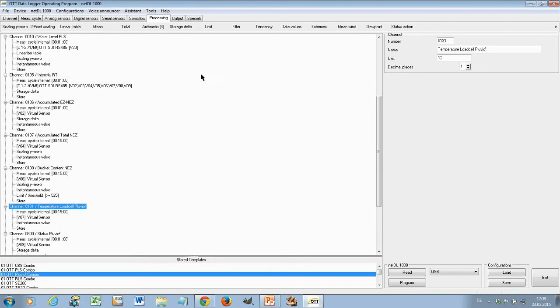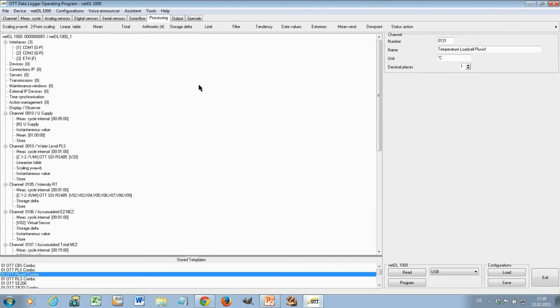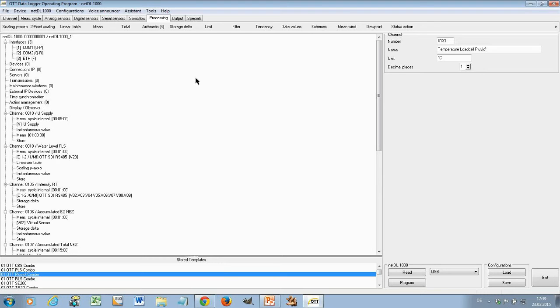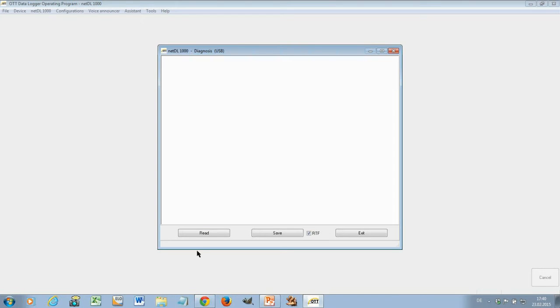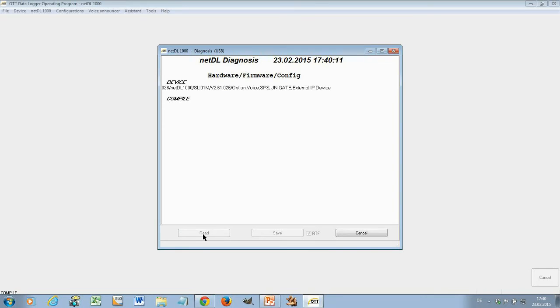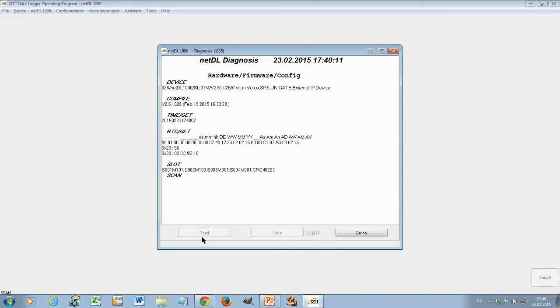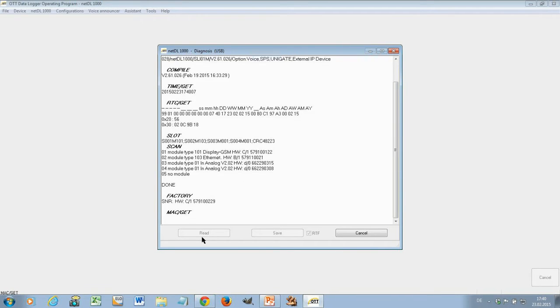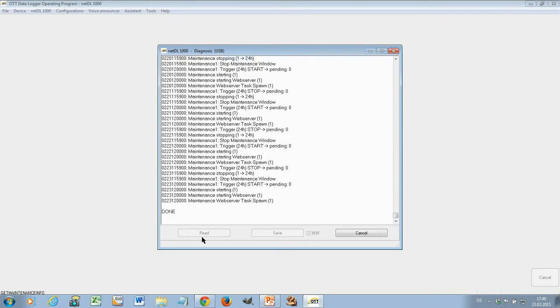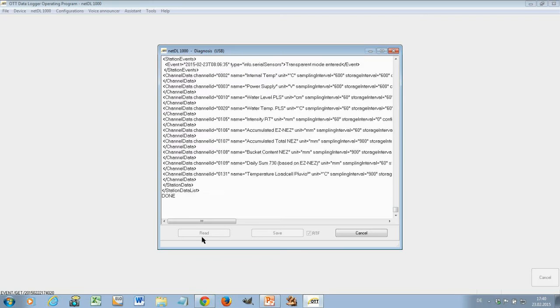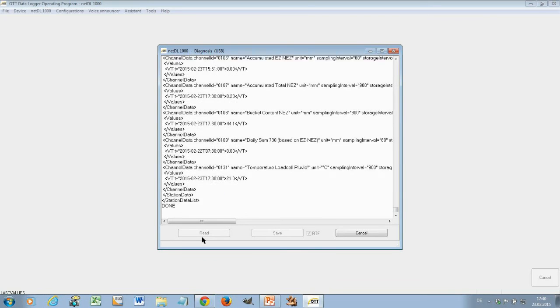Let's go to the next topic on our agenda, which is the diagnostic file. The diagnostic file is very helpful, especially in terms of communication to identify possible problems. In communication, there are a lot of obstacles which can prevent a successful communication, which could be a wrong password on an FTP server, a wrong address of an FTP server, a wrong path, and so on. And sometimes, it's not that easy to find where the problem is. The diagnostic file supports you here and helps you to get your system up and running in a very fast time. You go here to Tools and you see here Diagnosis. You choose Diagnosis and then you say Read. And now, the program reads out every information which is available in the NetDL. So, this takes now some time because it's retrieved any information which can be found within the data logger.